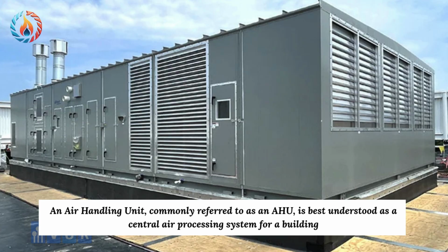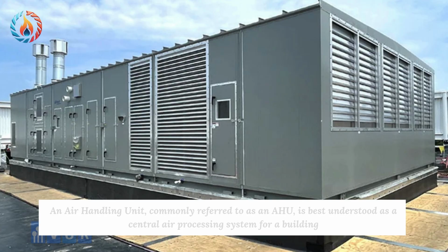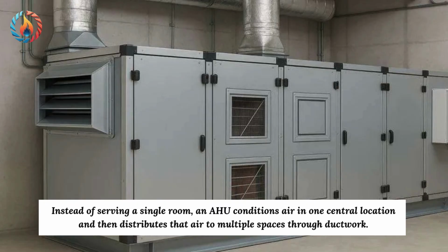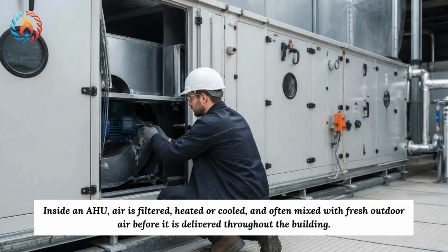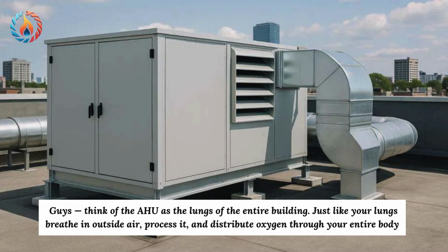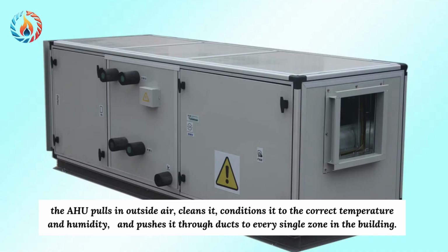An air handling unit, commonly referred to as an AHU, is best understood as a central air processing system for a building. Instead of serving a single room, an AHU conditions air in one central location, and then distributes that air to multiple spaces through ductwork. Inside an AHU, air is filtered, heated or cooled, and often mixed with fresh outdoor air before it is delivered throughout the building. Guys, think of the AHU as the lungs of the entire building. Just like your lungs breathe in outside air, process it, and distribute oxygen through your entire body, the AHU pulls in outside air, cleans it, conditions it to the correct temperature and humidity, and pushes it through ducts to every single zone in the building.